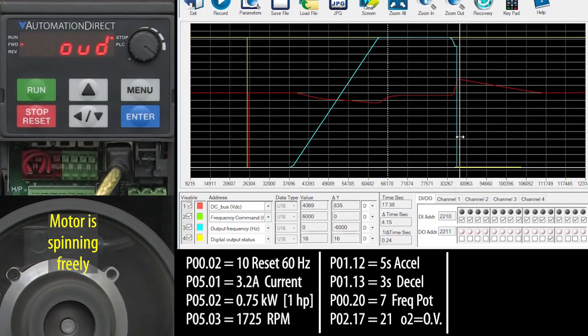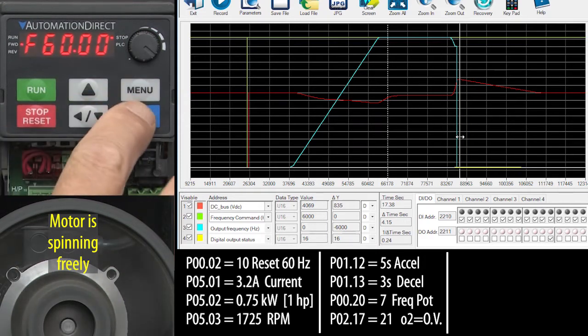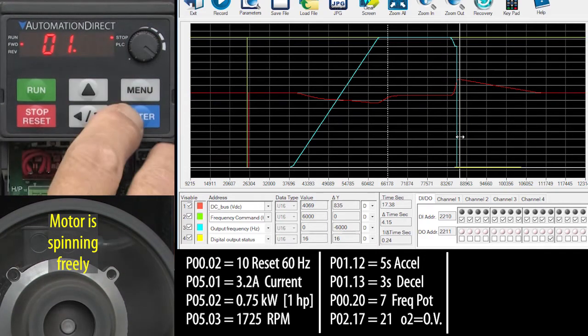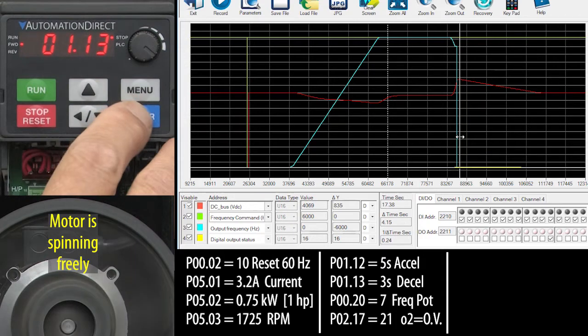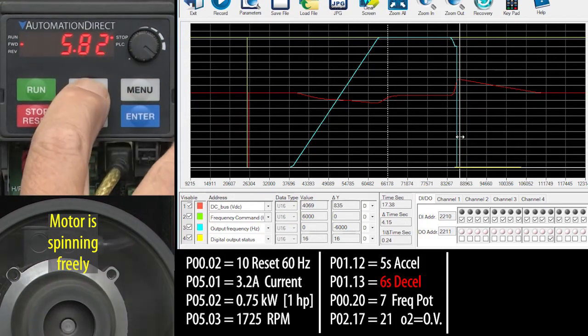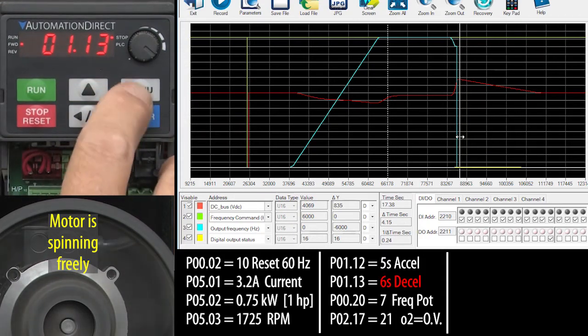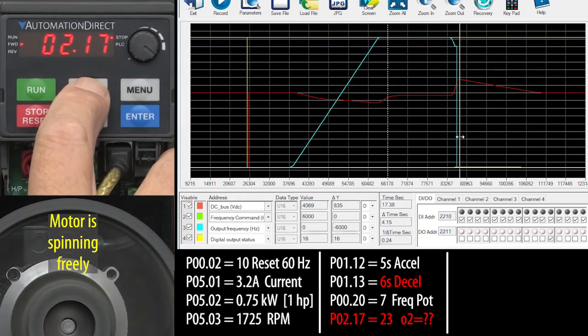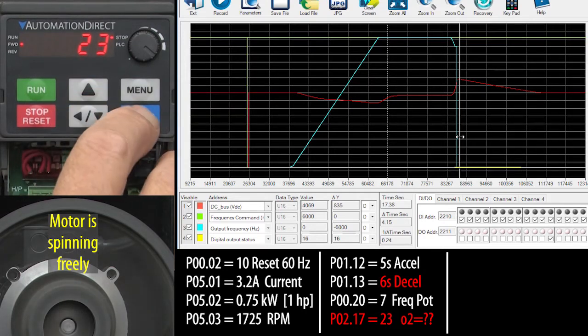To get rid of that fault, you can simply back off on the deceleration time to give the drive a chance to manage the extra energy. Let's double our deceleration time to 6 seconds. And I'm going to change output 2 to monitor something else. I'll tell you what it is in a minute.